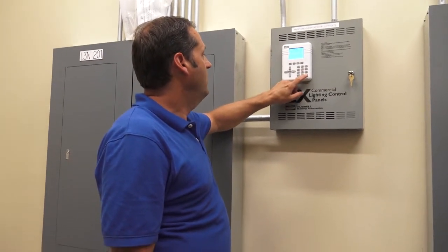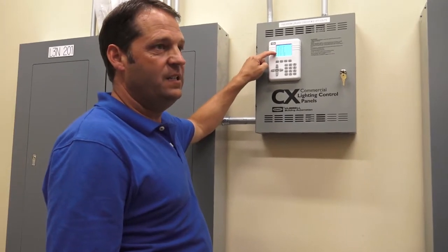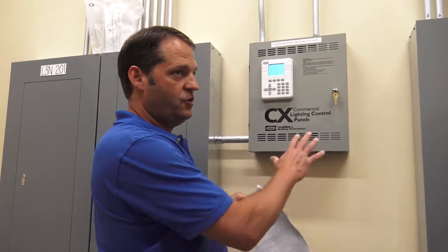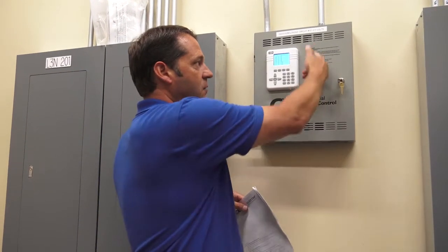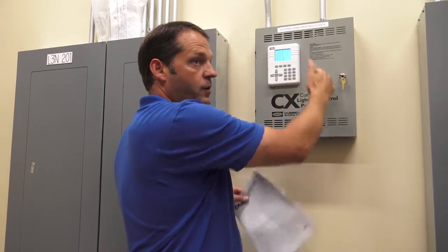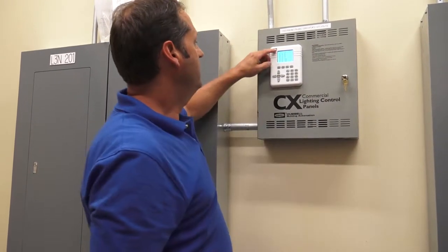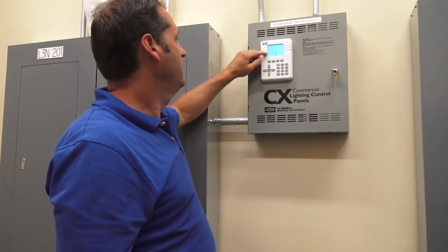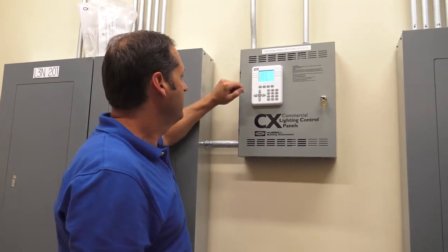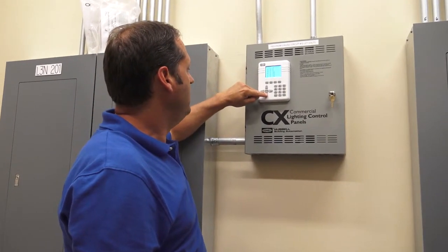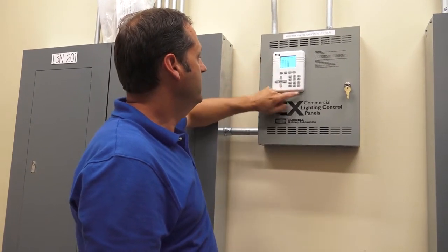Relay communication, all of your relays are online, meaning they're plugged in and functioning. Because this panel was sold with 8 relays, you can buy this panel and only install 3 relays. Or you can buy a 24 circuit panel, only install 9 relays. So it would show you 1 through 9 online, the rest of them not, because they're not installed. Some of this auxiliary stuff is not found because you have nothing hooked up to it.